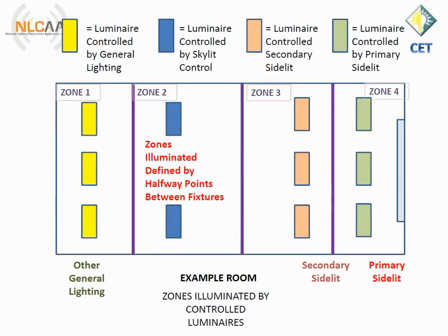Here are what are considered to be the zones illuminated by these controlled luminaires. And these are the areas where an acceptance test technician will be placing his light meter, somewhere in these four different zones, to make his check.